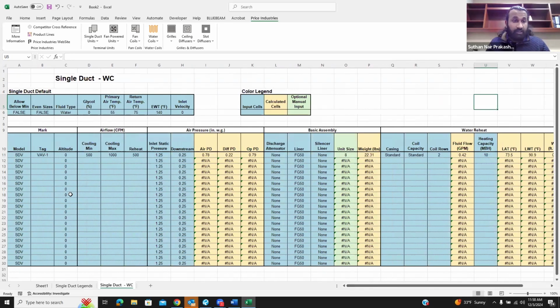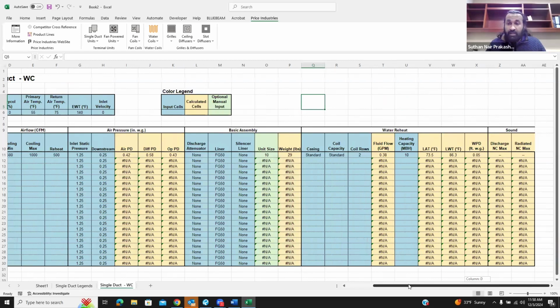And you can still use all the Excel rules here, like these blue color cells are blank cells. You can still use your rules to have multiple different CFMs listed below here, or you can create like 10 or 20 different VAVs at 100 CFM, like 500, 600, 1,500 to know what exactly the values are. For example, right now it says 1,500, and the unit size is 8. But if you want a unit size 10, you can still manually write it to 10, and the performance changes accordingly for the unit size 10. So this is one way.